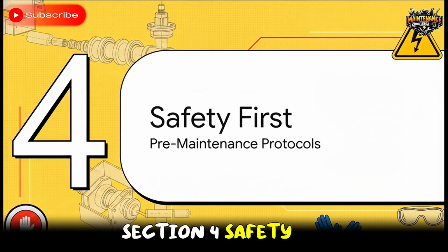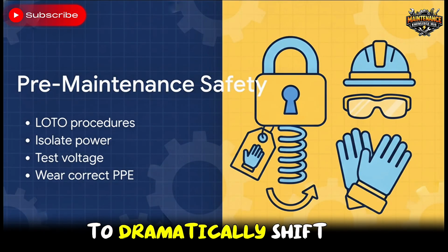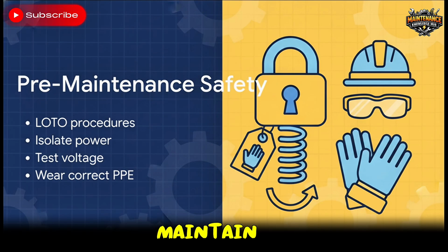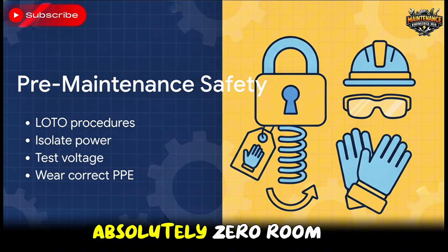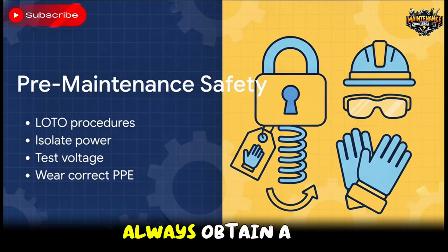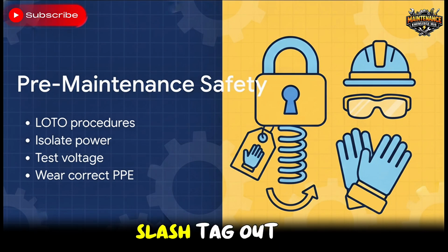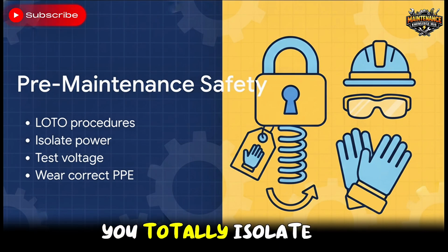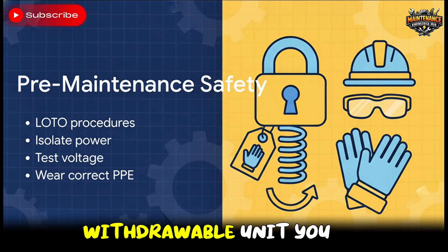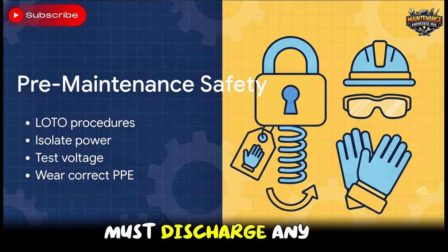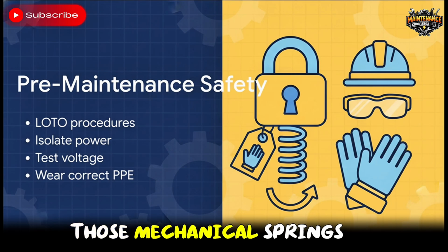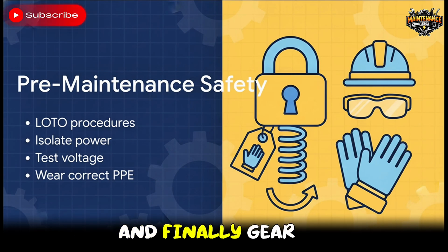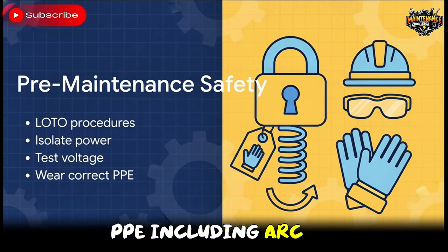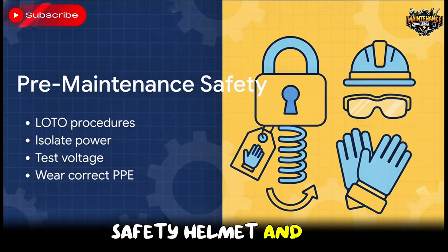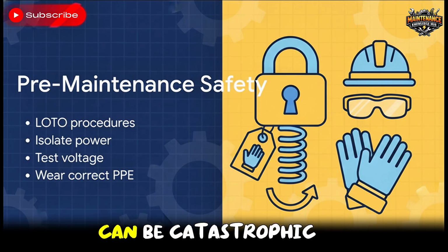Section 4. Safety first. Okay, we need to dramatically shift our tone here before we discuss how to actually maintain these machines. We are dealing with high-stakes, life-saving procedures right now, and there is absolutely zero room for error. First, you must always obtain a work permit and strictly follow Lockout/Tagout, or LOTO, procedures. You totally isolate the breaker from all power sources. If it's a withdrawable unit, you rack it out. You absolutely must discharge any stored spring energy before working. Those mechanical springs hold a terrifying amount of force. And finally, gear up. Wear the appropriate PPE, including arc-rated clothing, insulated gloves, a safety helmet, and safety glasses. Skipping even a single step here can be catastrophic.